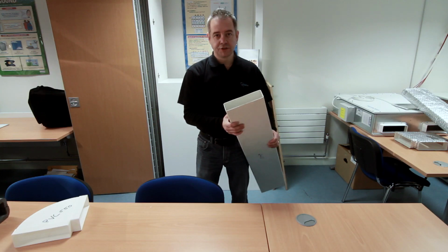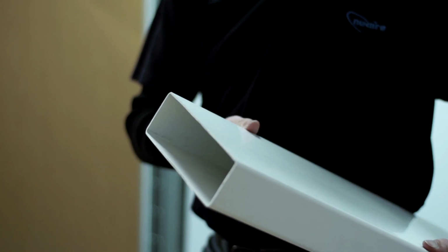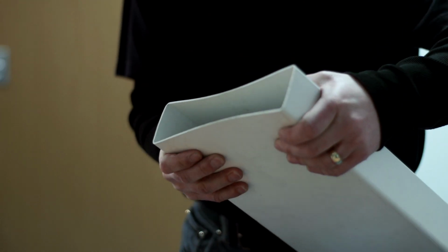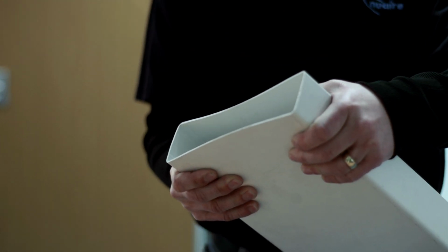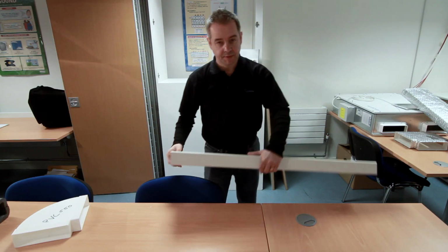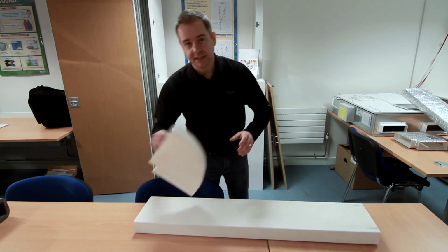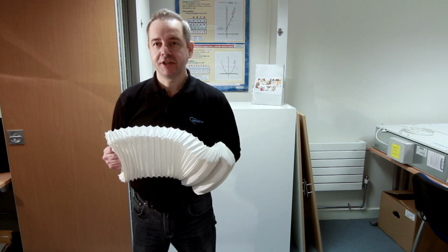A common issue when installing flat ductwork or rectangular ducting is its tendency to bow in the middle when connecting two pieces together. This can be overcome simply by using the correct ducting with guide vanes to hold it correctly. The use of flexible ducting is discouraged under the current version of the building regs due to its high resistive nature. The maximum amount of flexible duct you can use on any heat recovery system is 300 millimeters per leg.